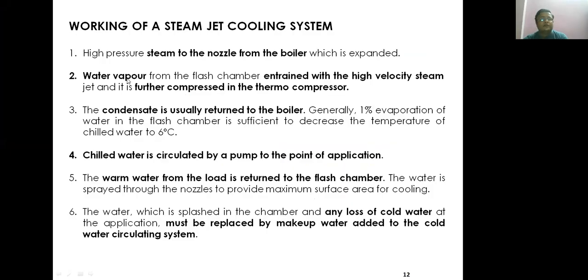This is the procedure for the steam jet cooling system. High pressure steam goes to the nozzle from the boiler, where it is expanded. Second, water vapor from the flash chamber is entrained with the high velocity steam jet and further compressed in the thermocompressor. The condensate is usually returned to the boiler. Generally, 1% of the evaporation water in the flash chamber is sufficient to decrease the temperature of the chilled water to 6 degrees. Chilled water is circulated by a pump to the point of application.